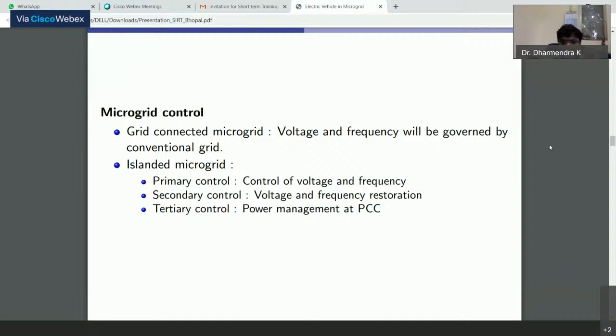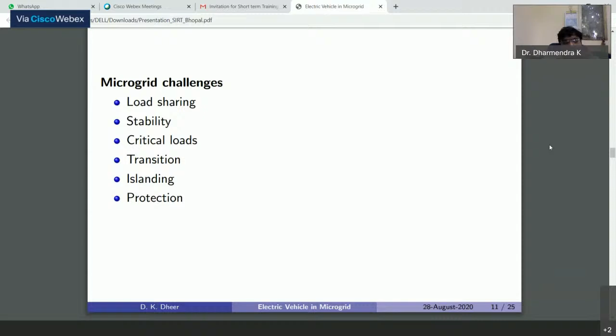Now let us see what the major challenges of the microgrid are. The challenges are load sharing: how generators will share the load. Then stability. In the islanded microgrid, it is not connected to the grid, so the inertia of the microgrid is very low compared to the main grid. So definitely the transient stability problem occurs, and sometimes a small signal stability problem also occurs. So these are the major challenges of the microgrid.